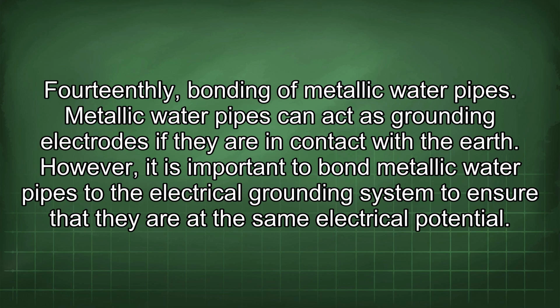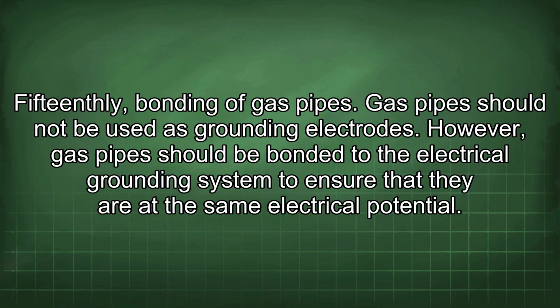Metallic water pipes can act as grounding electrodes if they are in contact with the earth. However, it is important to bond metallic water pipes to the electrical grounding system to ensure that they are at the same electrical potential. 15thly, bonding of gas pipes.